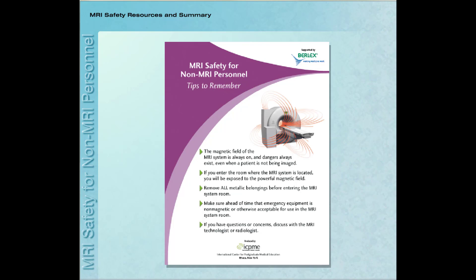Have a specific plan and perform practice drills periodically to ensure that everyone understands their role in the event of an emergency. The dangers associated with the powerful magnetic field of the MRI system should never be underestimated. Therefore, I encourage you to actively participate in the safety program at your facility by helping to inform and warn others about the potential hazards of the MRI environment.